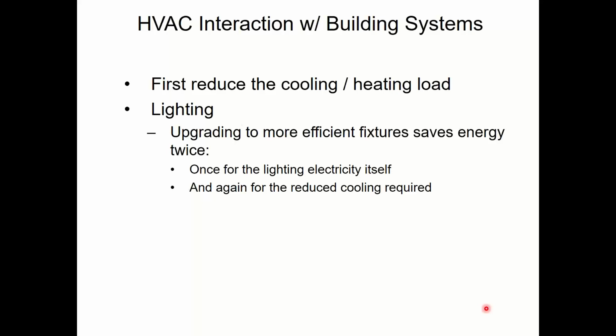For heating, I go the worst case the other way. Worst case for heating is that it's a super cold day outside. It's like 0 or whatever, right? No one's in the building giving off body heat. None of the lights are on, right? And there is no solar. It's nighttime. That's the worst case for heating. So changing the lighting doesn't affect my heating load calculation. Now, it will mean my heating will run a little bit more, but it doesn't change my calculation for sizing it, because my calculation is based on the worst case scenario, which means all the lights are off.